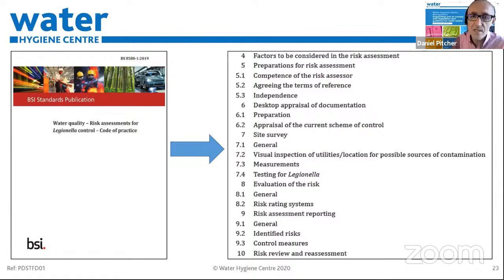Then there is the site survey - the visual inspection of the water systems within those buildings, completing monitoring and possibly Legionella testing as part of the risk assessment. There's a need for evaluation of the risk of that building and the water systems, with a defined risk rating associated with that water system, and finally reporting of those identified risks, the controls, and the need for reassessment.